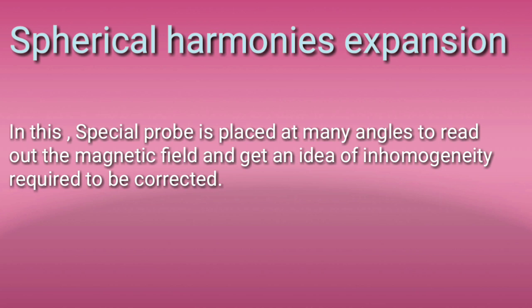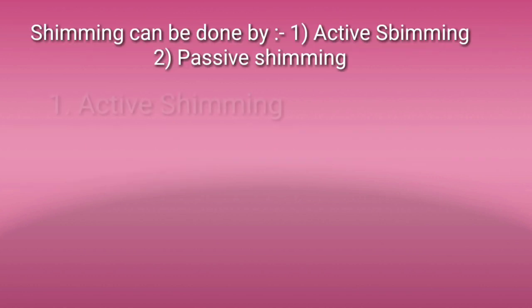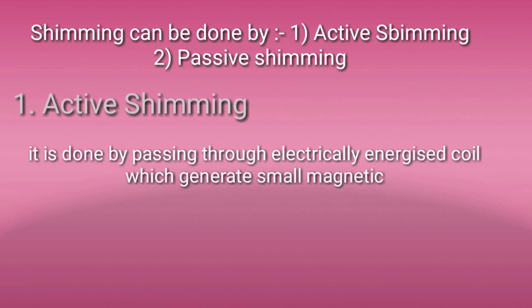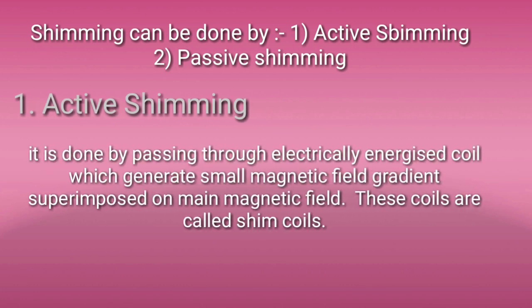To correct the inhomogeneity, there are two types of shimming: active shimming and passive shimming. In active shimming, electrically energized coils are used to correct and maintain the main magnetic field.